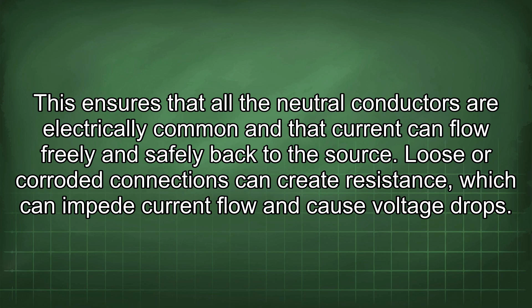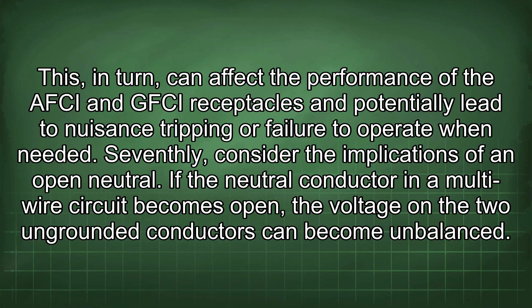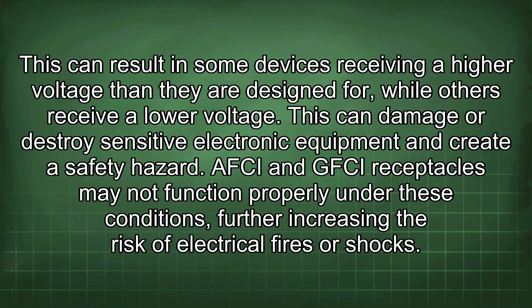Seventhly, consider the implications of an open neutral. If the neutral conductor in a multi-wire circuit becomes open, the voltage on the two ungrounded conductors can become unbalanced. This can result in some devices receiving a higher voltage than they are designed for, while others receive a lower voltage. This can damage or destroy sensitive electronic equipment and create a safety hazard. AFCI and GFCI receptacles may not function properly under these conditions, further increasing the risk of electrical fires or shocks.